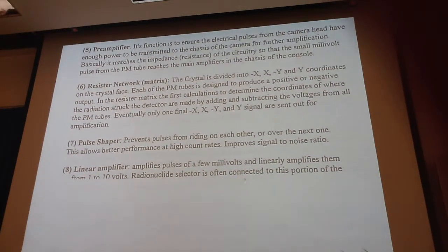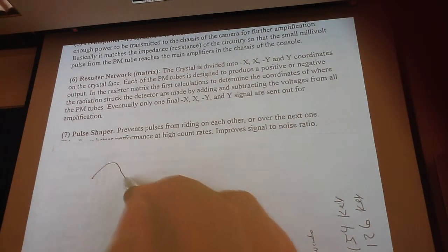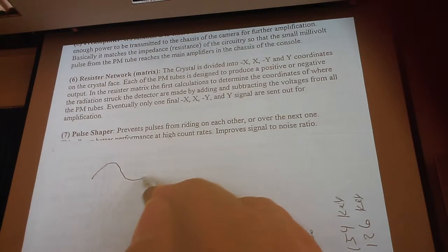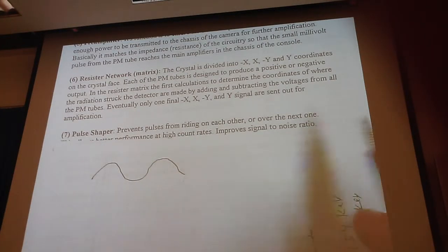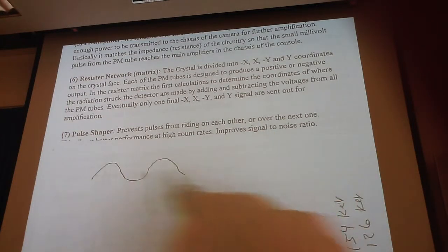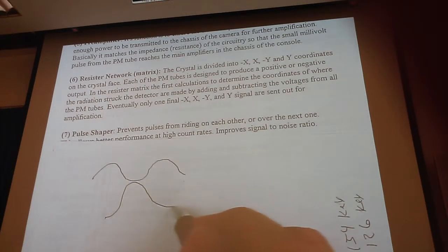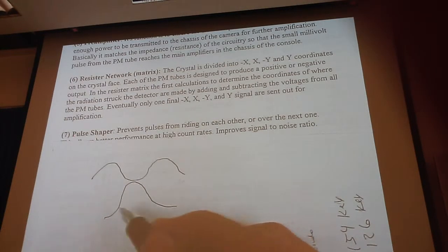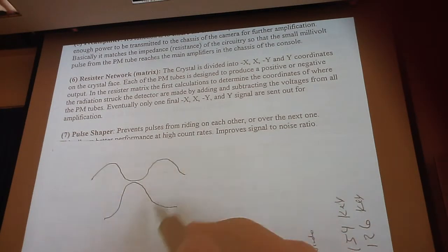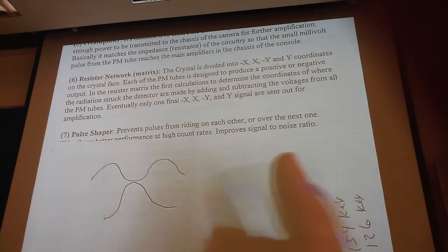It's like if you were at the ocean, you have one wave that's this big and then another one this big. They're arriving at about the same time, but sometimes one wave catches up to the other wave and then they're both added together, and then that's obviously rejected. So the pulse shaper just makes sure that stuff doesn't get distorted when it's sent to the gamma camera.